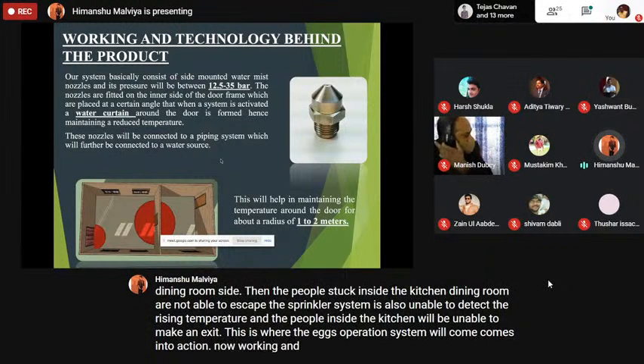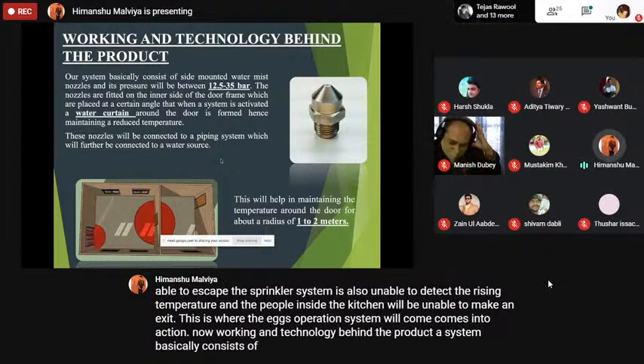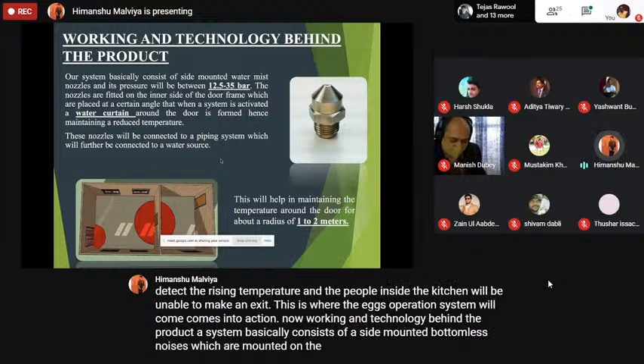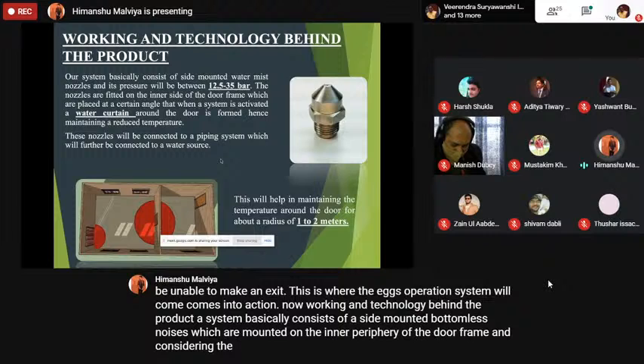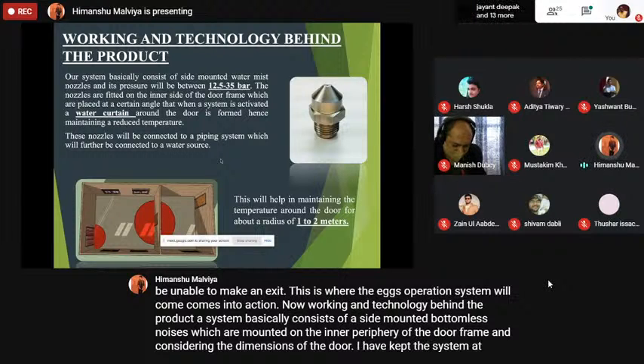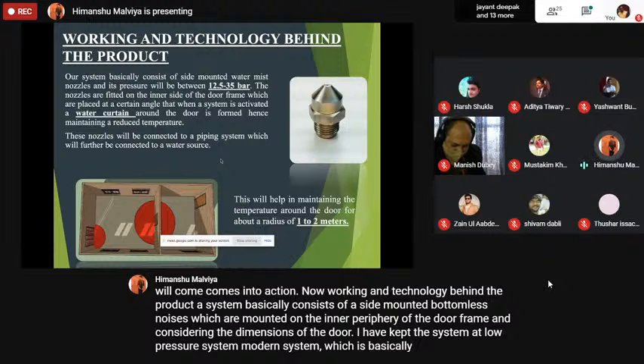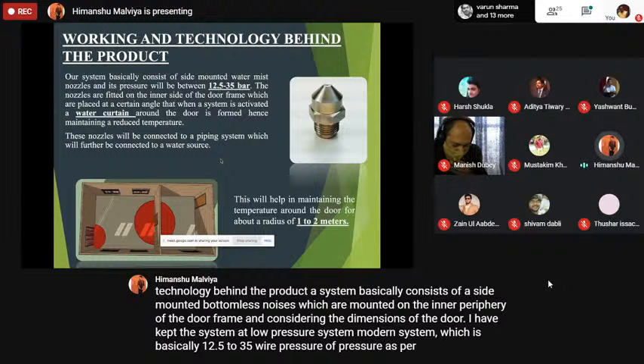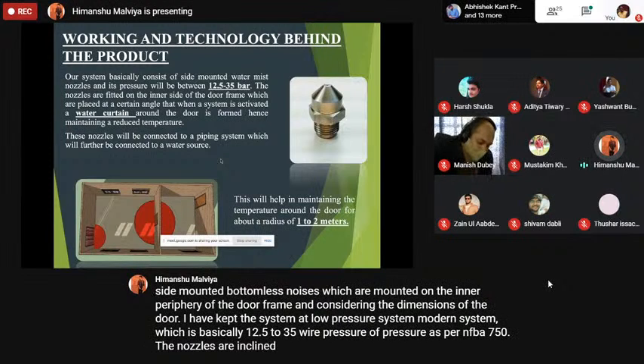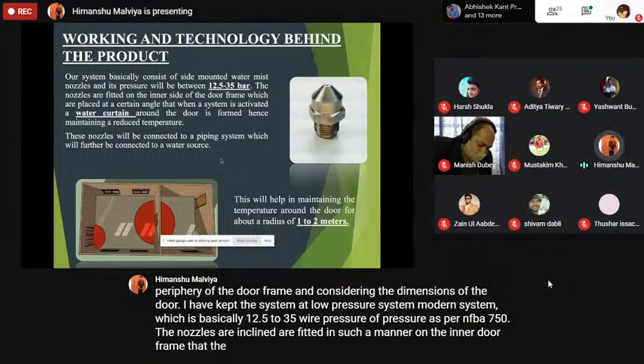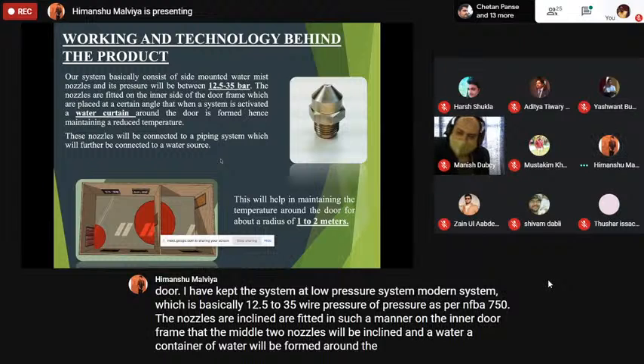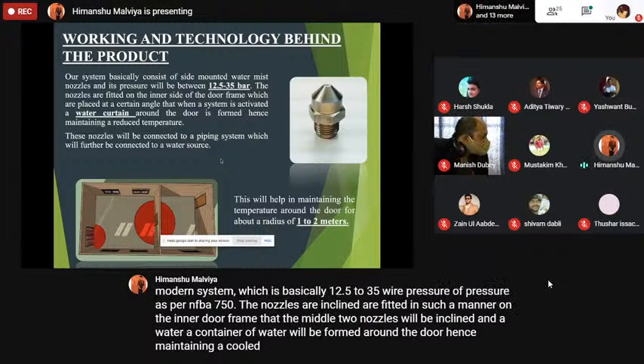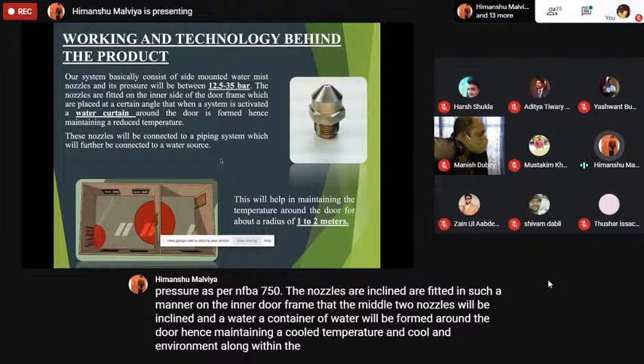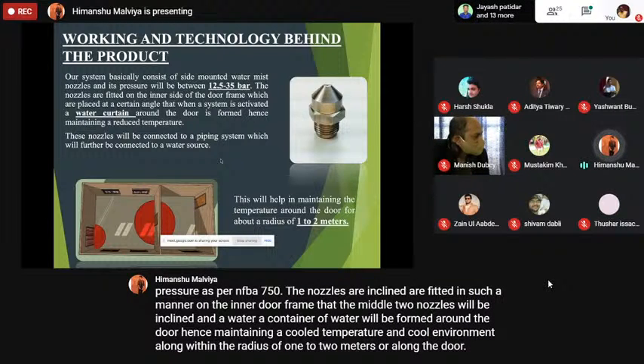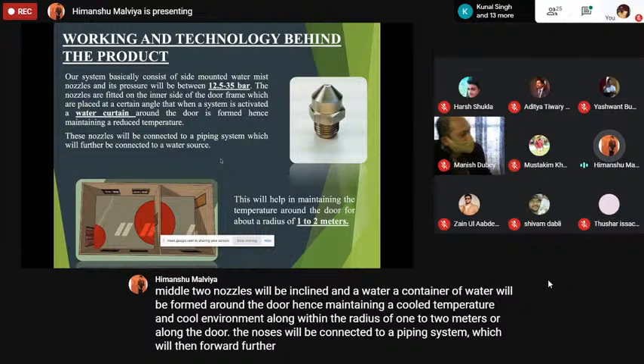Now, the working and technology behind the product. The system basically consists of side mounted water mist nozzles which are mounted on the inner periphery of the door frame. Considering the dimensions of the door, I have kept the system as a low pressure water mist system, which is basically 12.5 to 35 bar pressure as per NFPA 750. The nozzles are fitted on the inner door frame in such a manner that the middle two nozzles are inclined, and a curtain of water is formed around the door, hence maintaining a cooled temperature and environment within a radius of 1 to 2 meters along the door. The nozzles will be connected to a piping system, which will then be connected to the water source.